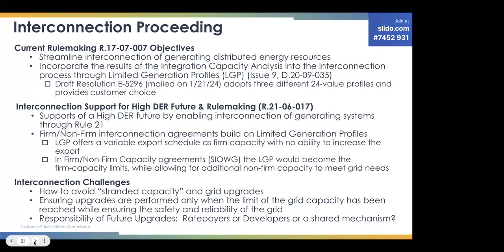As of yet, we do not really have a proceeding for Rules 15 and 16. Most of our efforts have been on interconnection. The objective of our current Rule 21 proceeding is to streamline interconnection of DERs. In particular, for generation, we're implementing limited generation profiles to allow greater use of existing grid capacity and avoid distribution grid upgrades. Most recently, a draft resolution on LGP was mailed for comments on January 21st, 2024. It resolved many issues, including the granularity of profiles allowed for the LGP interconnection options. We are still waiting for standards regarding scheduling to be published.